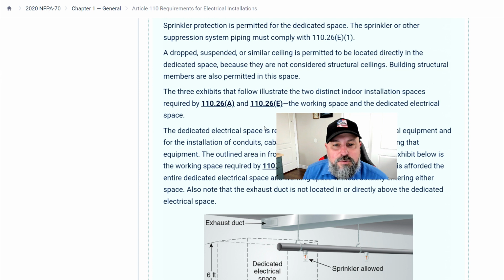The 3 exhibits that follow illustrate the 2 distinct indoor installation requirements of 110.26A and 110.26E, the working space and dedicated electrical space. The dedicated electrical space is reserved for the installation of electrical equipment and for the installation of conduits, cable trays, and so forth, entering or exiting that equipment. The outlined area in front of the electrical equipment in the exhibit below is the working space required by 110.26A. Note the sprinkler protection is afforded the entire dedicated electrical space and working space without actually entering either space. Also note the exhaust duct is not located in or directly above the dedicated electrical space.